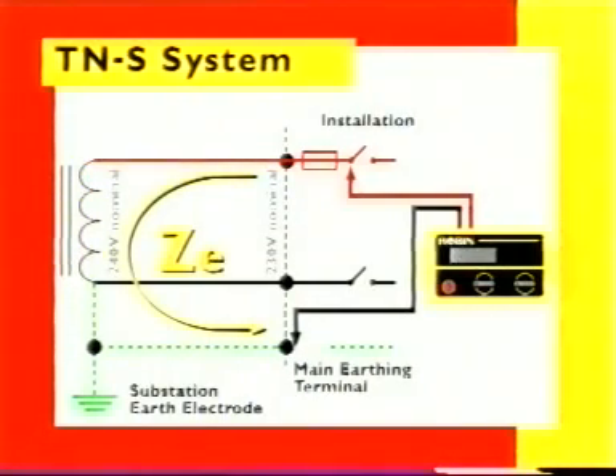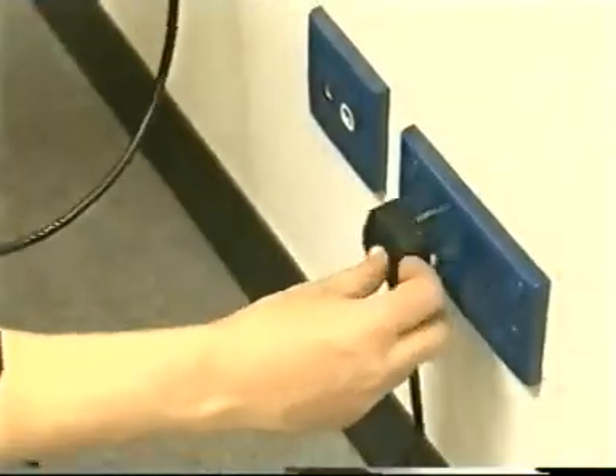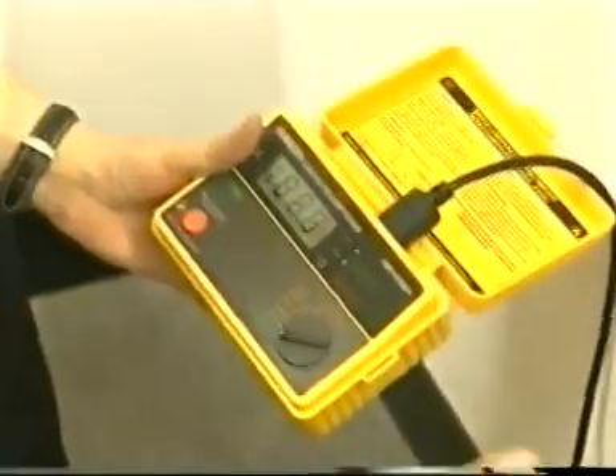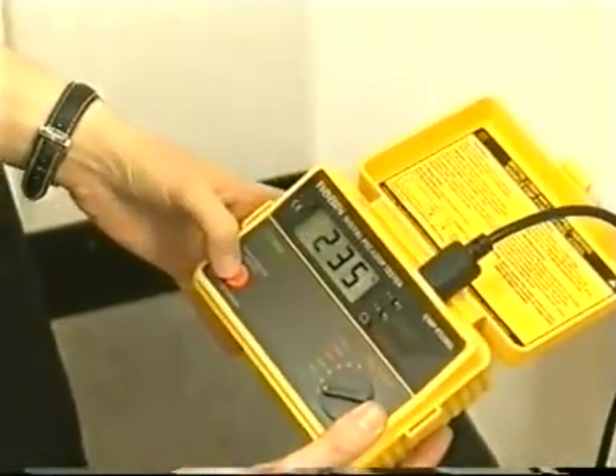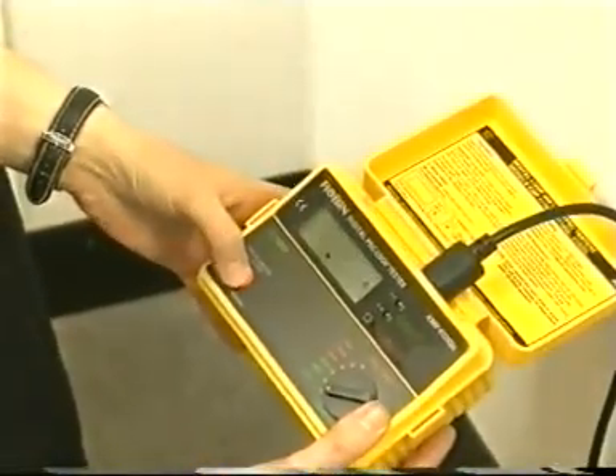With the installation main earthing terminal reconnected to the means of earthing, the supply is reinstated and a ZS measurement taken at all outlets on the circuits. The highest recorded impedance is recorded for each circuit.